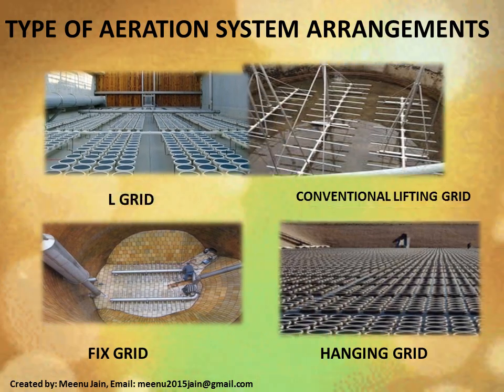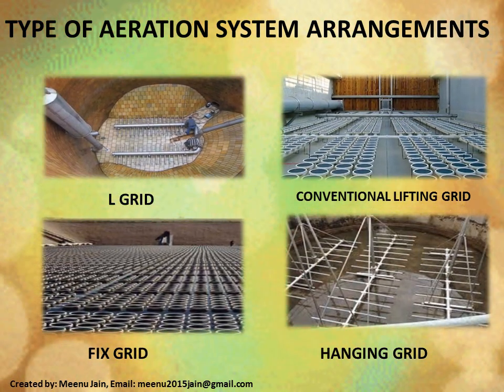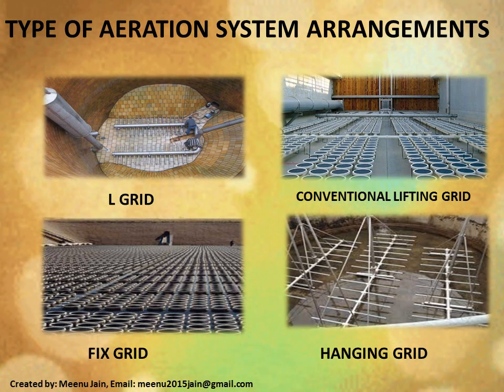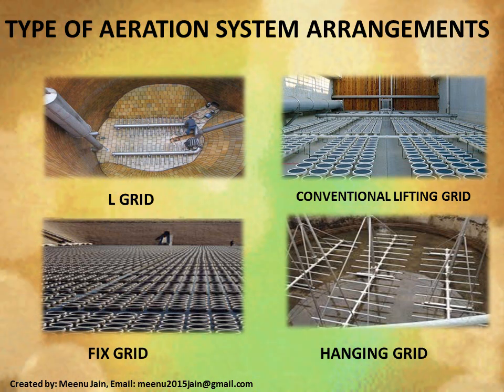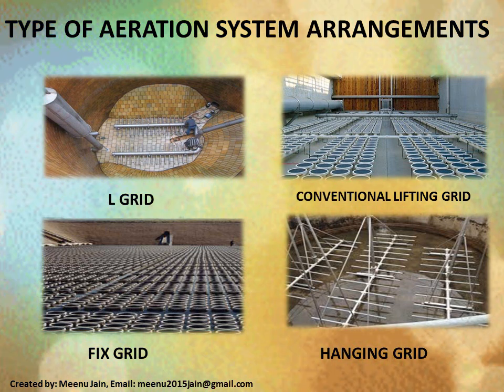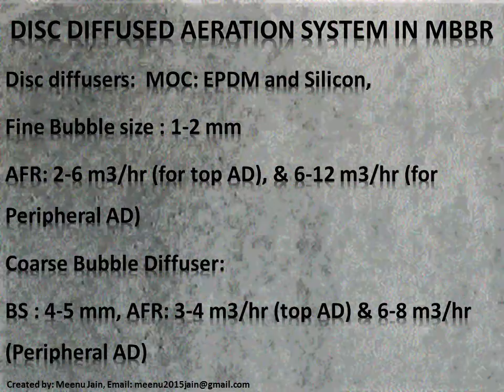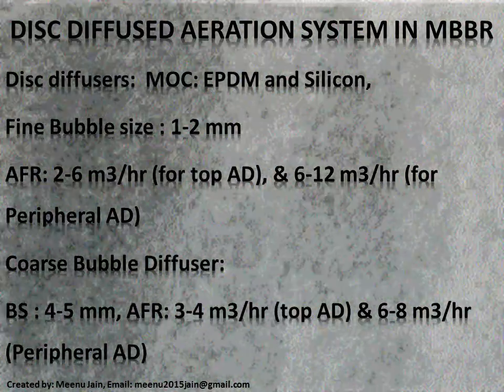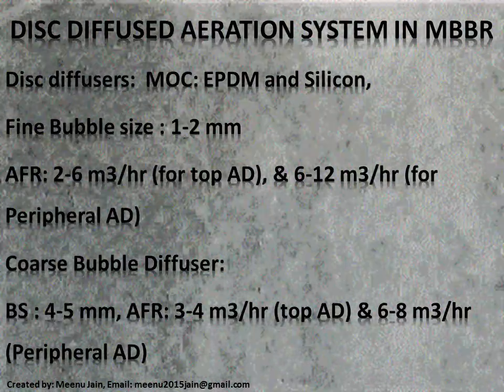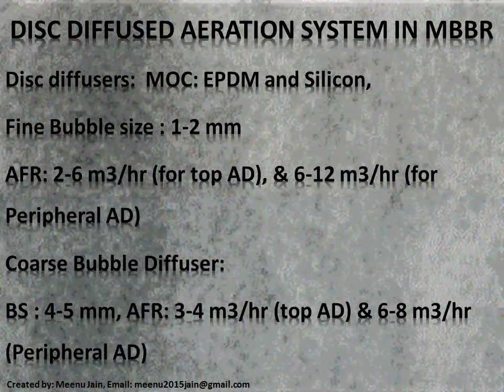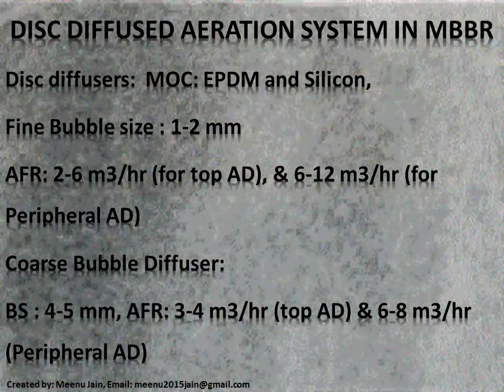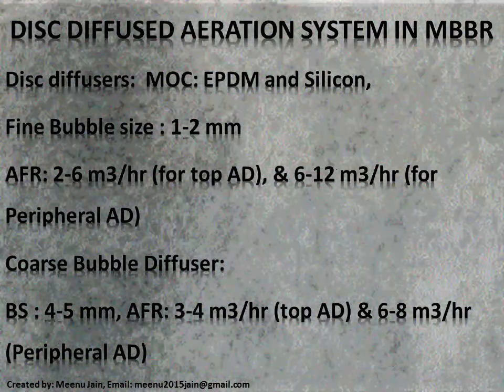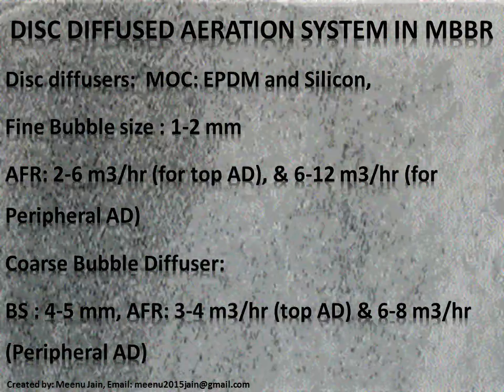There are many arrangements available for diffuser aeration systems, including L-grid, conventional lifting grid, fixed grid, and hanging grid, used as per the process and operation maintenance requirements. In the disc diffuser system, small discs are placed on top of a pipe. The materials of construction for these discs are mainly EPDM — ethylene-propylene diene monomer, or simply synthetic rubber — and silicone. Disc diffusers are available as both fine and coarse bubble diffusers.